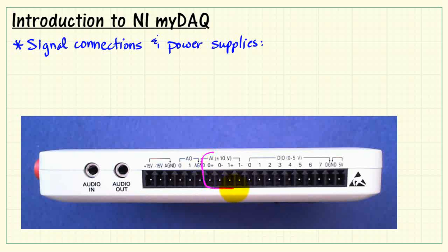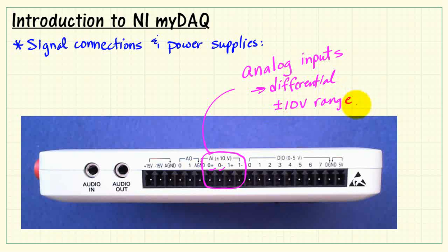We also have two analog input channels. These analog inputs are differential, so we have both a plus side and a minus side, so we're measuring the potential difference between those two inputs. The analog inputs have a plus-minus 10 volt range, and again, that's indicated right there on the face of myDAQ.